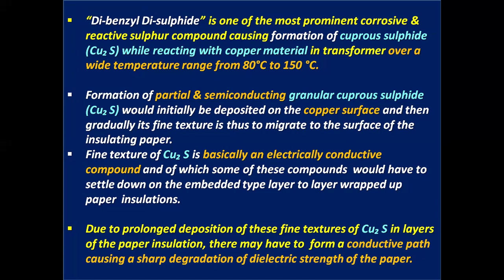Partial and semiconducting granular cuprous sulfide would initially be deposited on the copper surface and then gradually its fine texture would migrate to the surface of the insulating paper. The fine texture of Cu2S is an electrically conductive compound, and some of it would settle on the embedded layer-to-layer wrapped paper insulation.